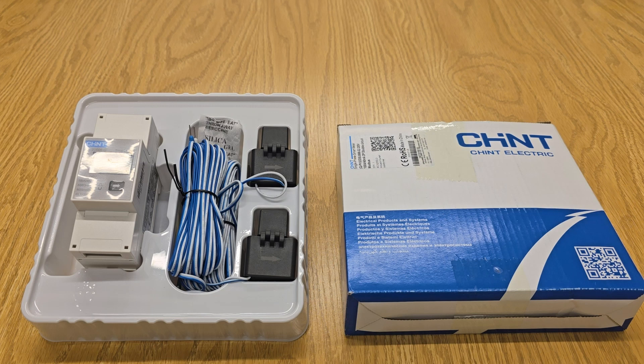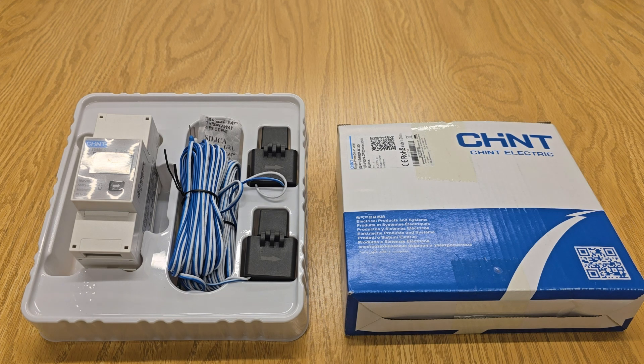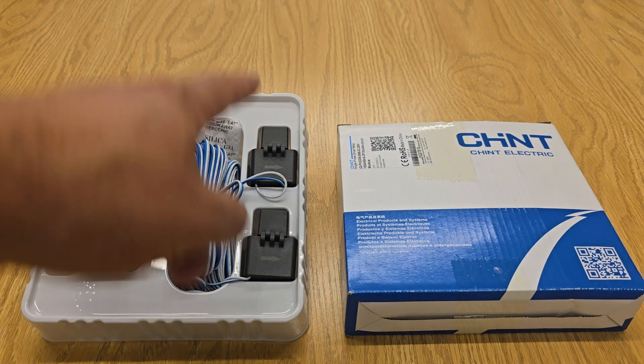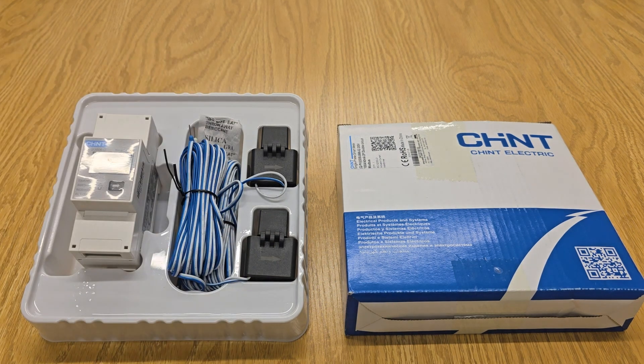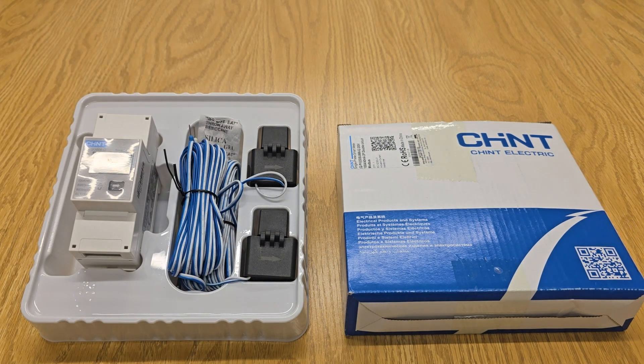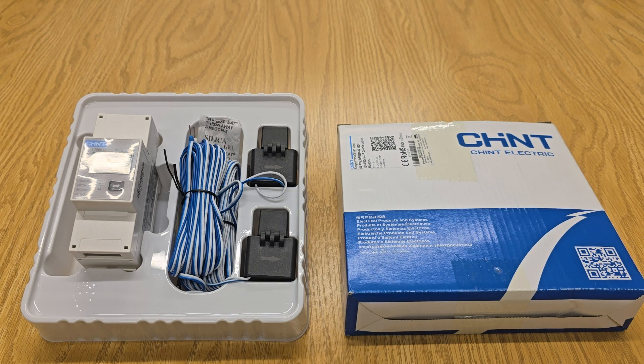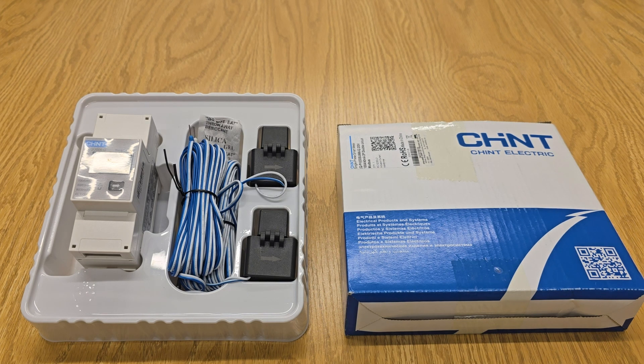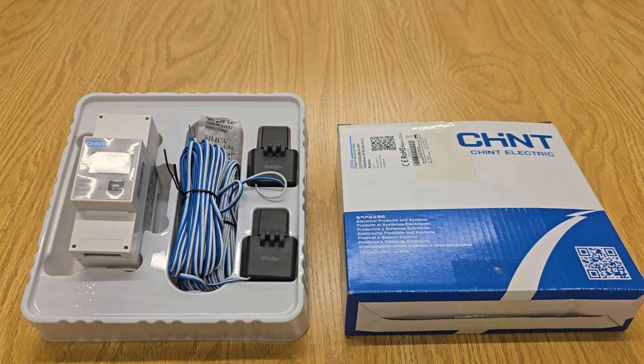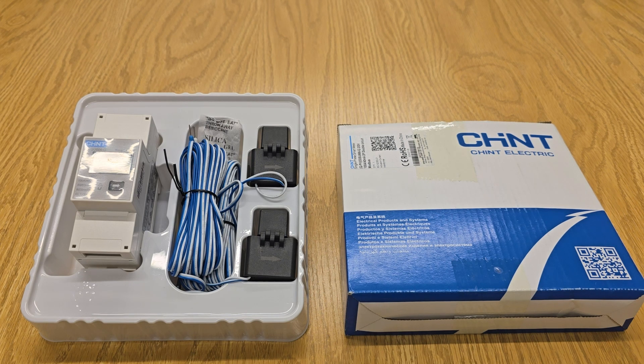You're going to get two CT clamps: one for the grid supply, so that's the main tail between the main fuse cutout and the meter of the property, and the other CT clamp is going to go around a live cable, not the whole cable, but a live cable of the PV system, so you can now monitor the PV.